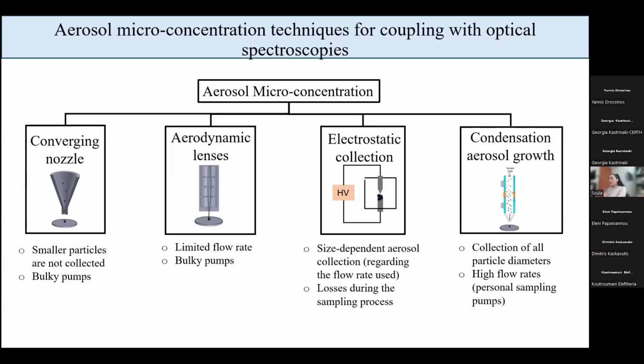But in this case, we cannot effectively concentrate smaller particle sizes because of the inertia. And in most cases, we will have to use big bulky pumps to be able to handle big pressure drops. Another way to microconcentrate aerosols is the use of aerodynamic lenses, where we can effectively concentrate smaller sizes too. But in this case, we definitely have to use big bulky pumps to handle the high pressure drop. Another way to microconcentrate is by using electrostatic collection, where we charge the particles and then we collect them on the surface of the opposite charge.